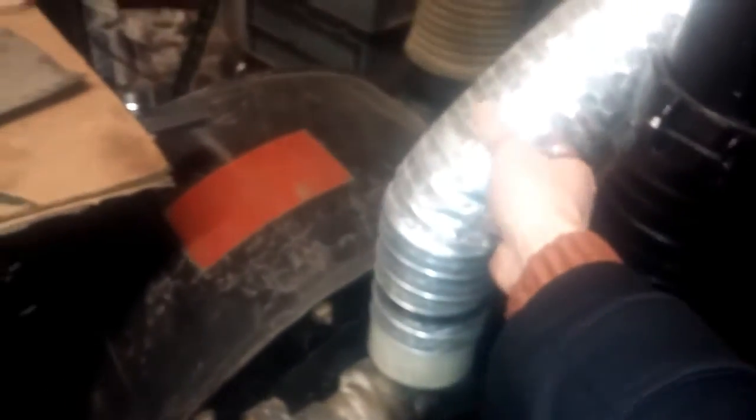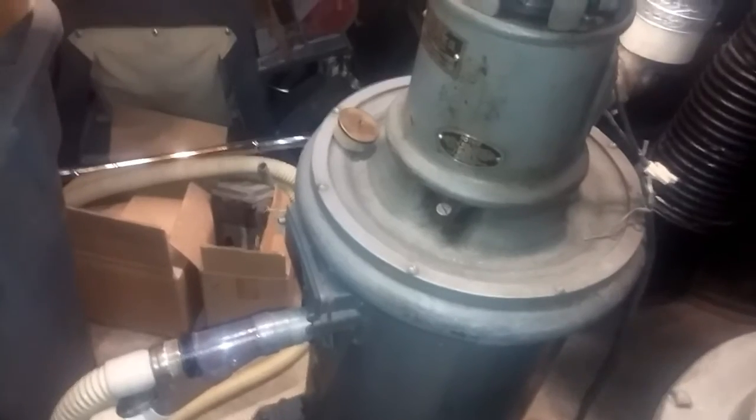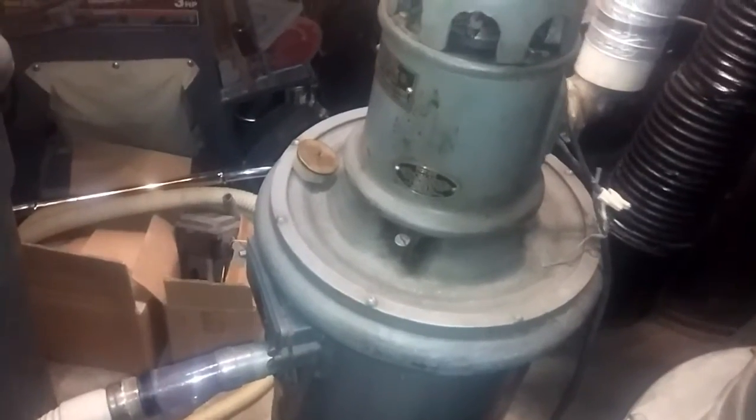You can see how much moisture is in the exhaust — you can see it condensing in there. It's pulling the exhaust through the single impeller and going out through this dryer hose that's connected to the outside of the building. The exhaust gas shouldn't be explosive or combustible — this is just the by-product of combustion — so you can run it through without too much concern for explosion.